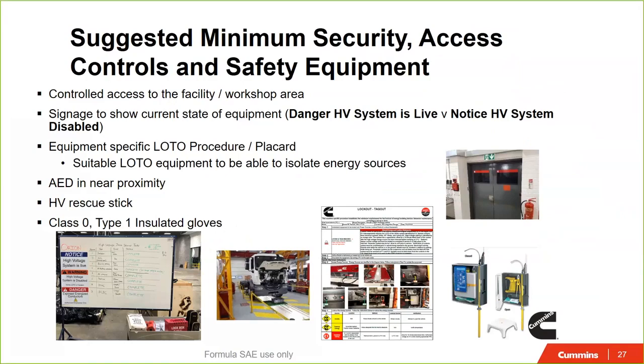We always try to have an AED nearby, certainly within 50 yards of where we're doing exposed work. HV rescue sticks, shown in the bottom right corner, are designed to pull a victim away from the electric source. For our batteries - and you'd have to do the calculations based on your arc incident rate - we look at using Class 0, Type 1 insulated gloves.